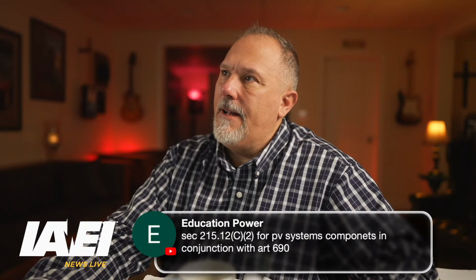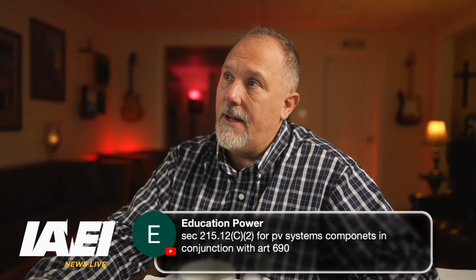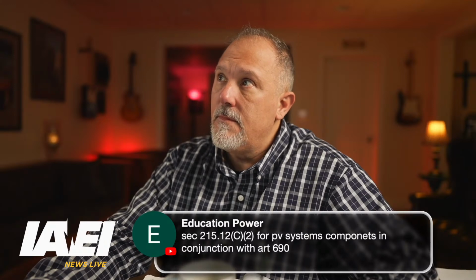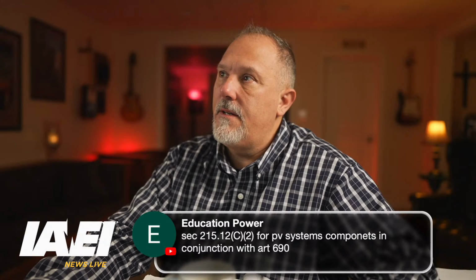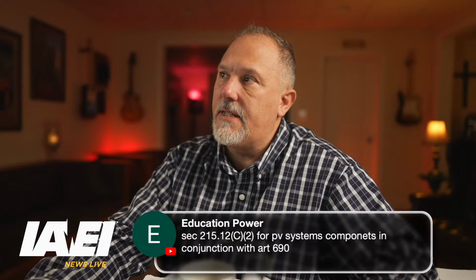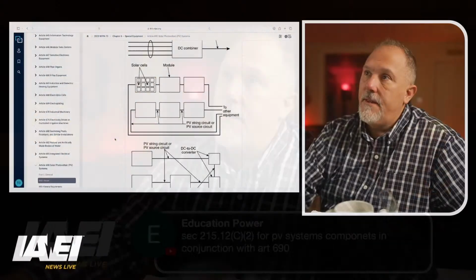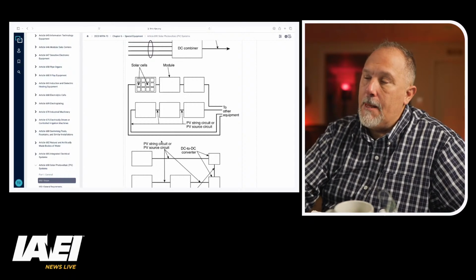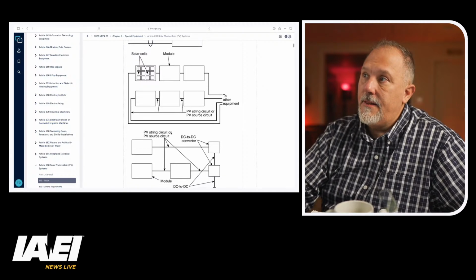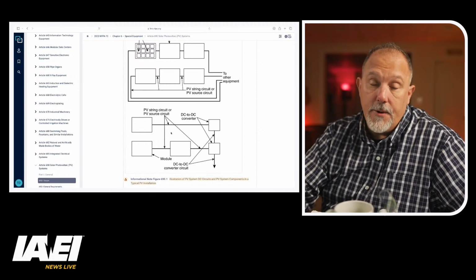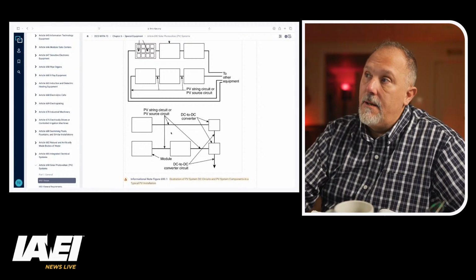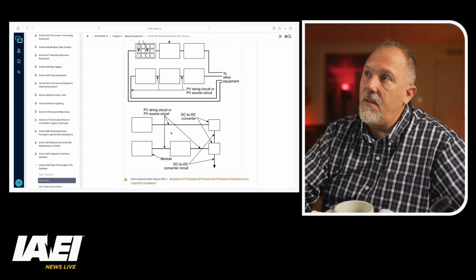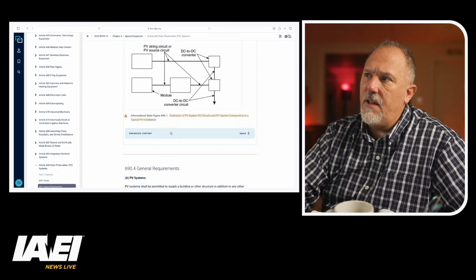That's in transformers. We can do a whole other section on this, but I would argue, Robert, that they have a PV source circuit. They've defined it as a PV source circuit. That's what they did. PV string circuits and PV source circuits. They'll tell you those are not feeders. Although I disagree. They meet the definition of a feeder to a T, but they don't call them that. They call them PV source circuits and PV string circuits. So the question would be, if they're not a feeder, then I would not be following that reference that you made. I don't know, Robert. They didn't add clarity when they created new terms.